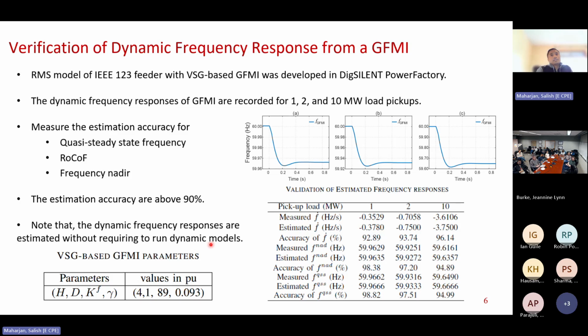So for that, what we did is we developed an RMS model of the grid forming inverter in DIgSILENT PowerFactory. And then we recorded the frequency response of these grid forming inverters when we subject load changes to them. The load change experimented was a change of 1, 2, and 10 megawatts of load with the grid forming inverters, and their frequency response was recorded. And from this recording, we can easily measure the steady state frequency, the ROCOF, and the frequency nadir.